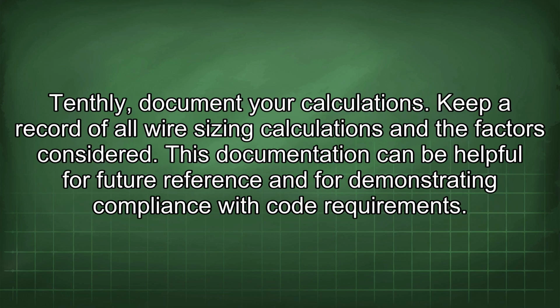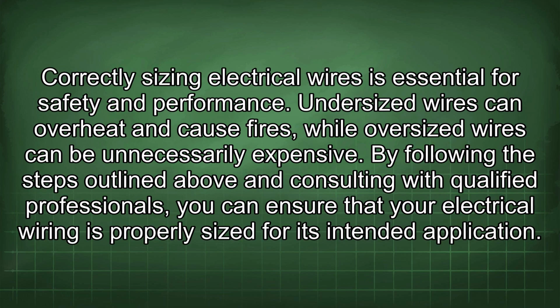Tenthly, document your calculations. Keep a record of all wire sizing calculations and the factors considered. This documentation can be helpful for future reference and for demonstrating compliance with code requirements. Correctly sizing electrical wires is essential for safety and performance. Undersized wires can overheat and cause fires, while oversized wires can be unnecessarily expensive. By following the steps outlined above and consulting with qualified professionals, you can ensure that your electrical wiring is properly sized for its intended application.